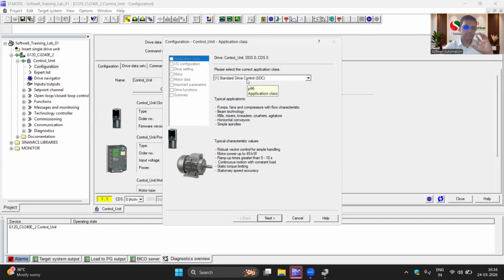What is the rule? First, cursor position — you can see in the yellow pop-up, P96. This is important if you have no software tools and want to do commissioning using the keypad; you need the cursor position at P96. The details: one option is SDC, meaning your motor capacity is up to 45 kilowatts, not more.